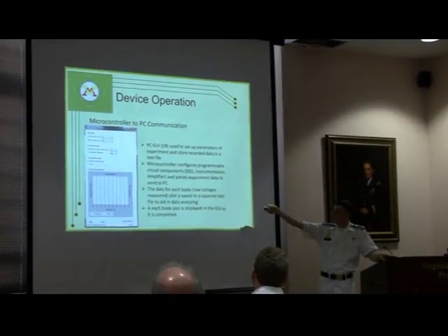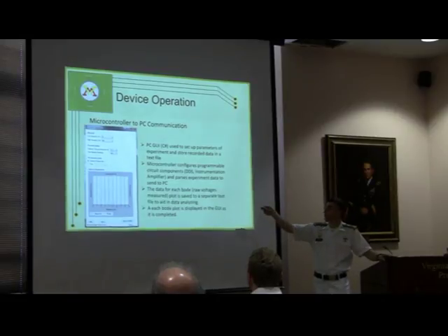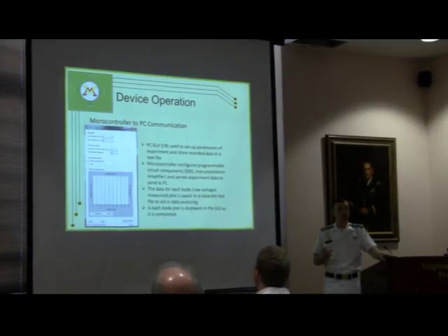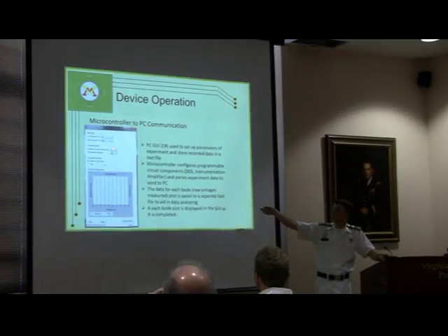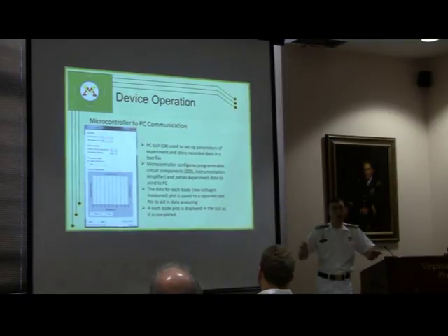In this middle section, you choose basically how long you'll be taking readings. What this essentially does is this controls how many data points per frequency. So say it's at 0.1 right now, so with a current sampling frequency of 1 kilosamples per second, it's going to take 100 samples because you're taking all your samples over a period of 0.1 seconds. So this is just controlling how many samples you take per frequency. And you'll take this same number of samples for each frequency on that range that you selected.